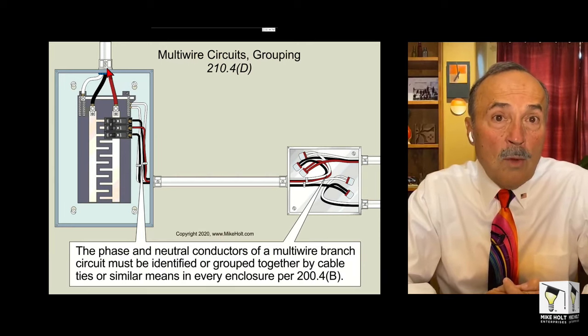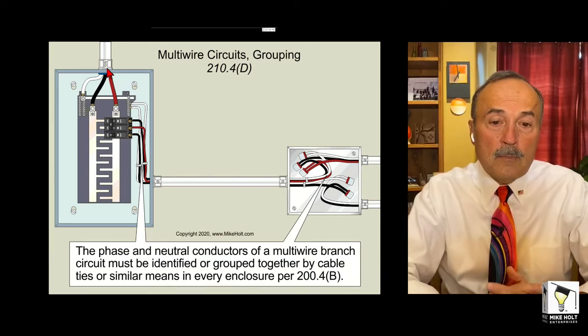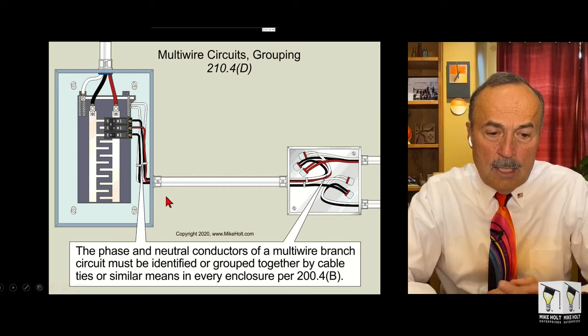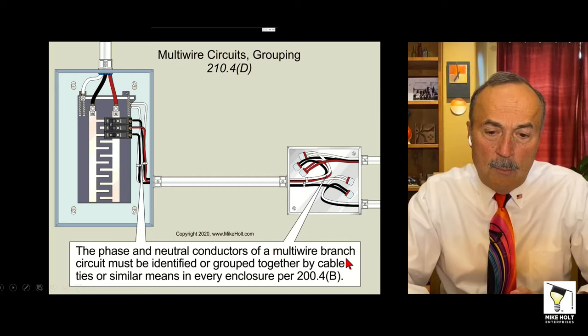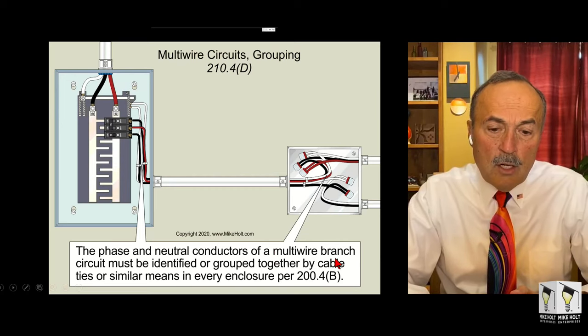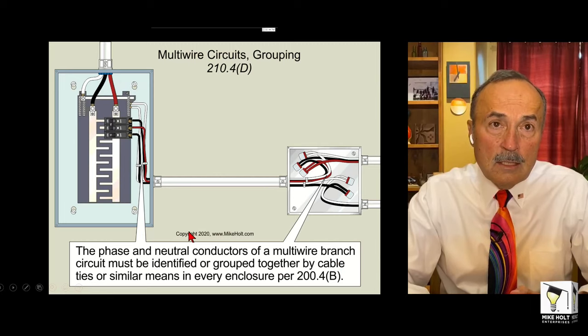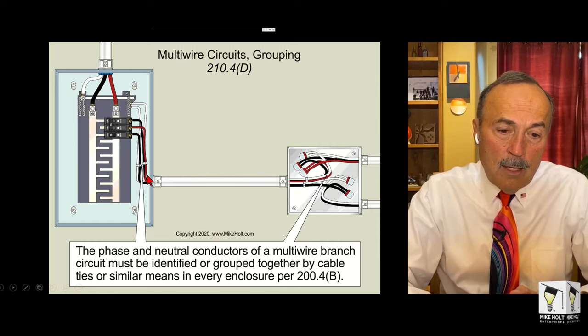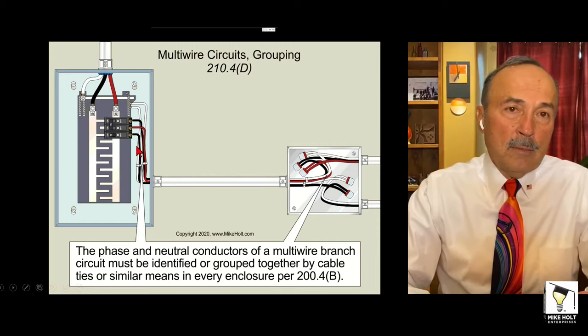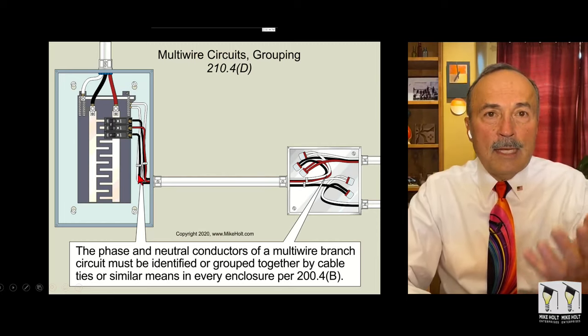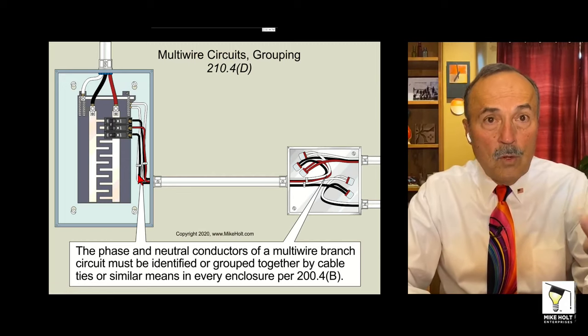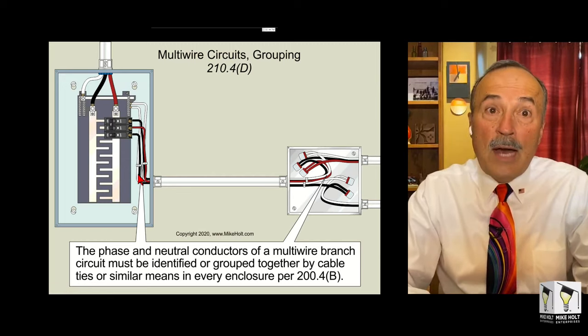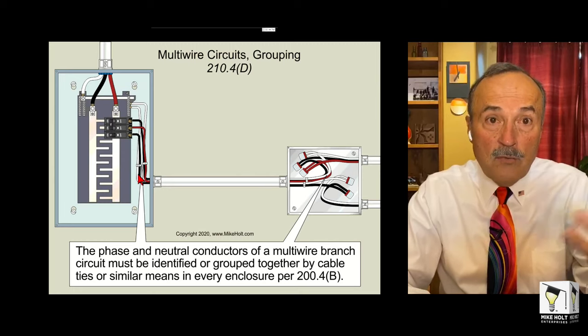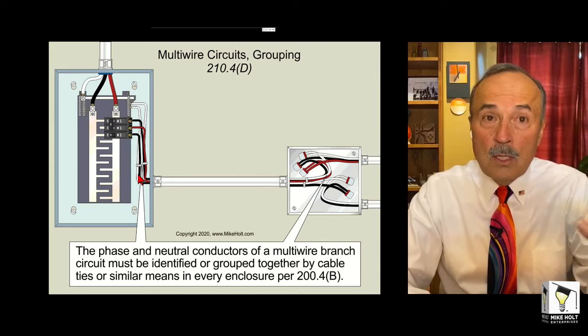Some other things about multi-wire branch circuits, because of the hazards in 210.4(D): the phase and neutral conductors of a multi-wire branch circuit must be identified or grouped together by cable ties or similar means in every enclosure. Now there's an exception to this. If you're coming into a raceway and there's only two hots and a neutral, you don't need to identify them. You don't have to group them because it's obvious. So if you bring in some MC cable or armor cable, well, it's obvious.